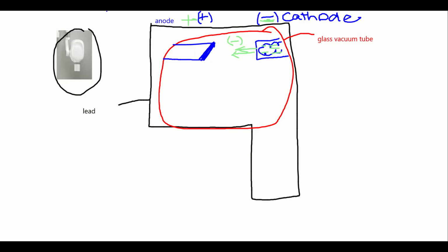Anyway, when you push the button to take the x-ray, you're releasing the electrons and the electrons automatically come over to the side. Now, do we want the electrons to actually engage with and connect with the protons on the positive side? We don't, because if we let them connect with and engage with them, then we lose the energy. So what we want is we actually put something in the way, and that something is a piece of metal that we put right here.